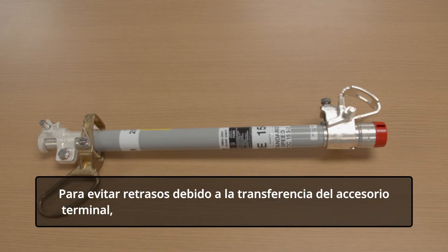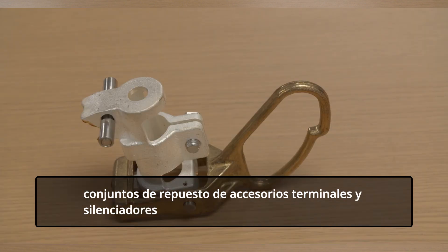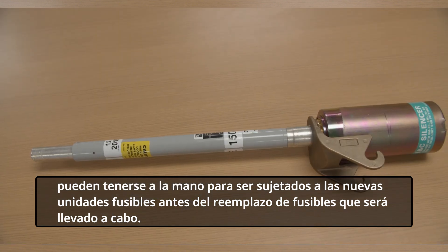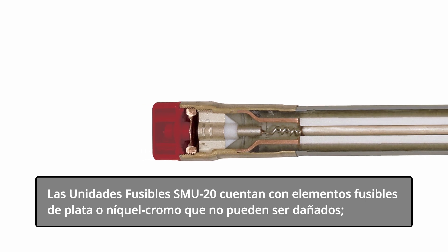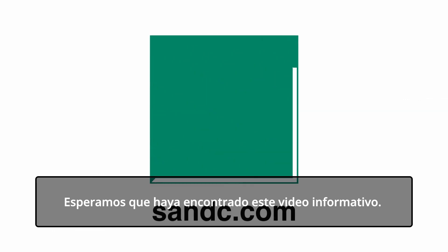To avoid delay due to transferring of end fittings, spare sets of end fittings and silencers may be kept on hand for attachment to new fuse units before refusing is to be performed. SMU-20 fuse units have silver or nickel chrome fusible elements that are non-damageable. Consequently, there is no need to replace unblown companion fuses on suspicion of damage following a fuse operation. We hope you have found this video informative.